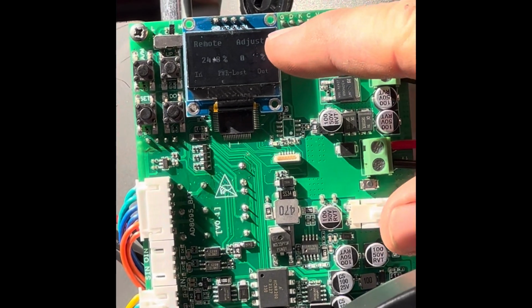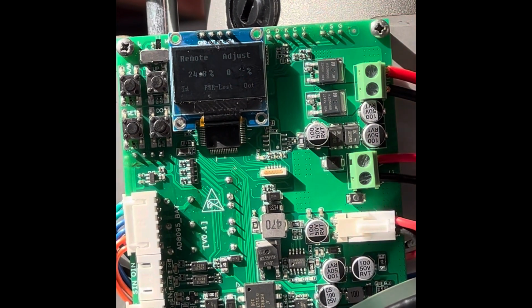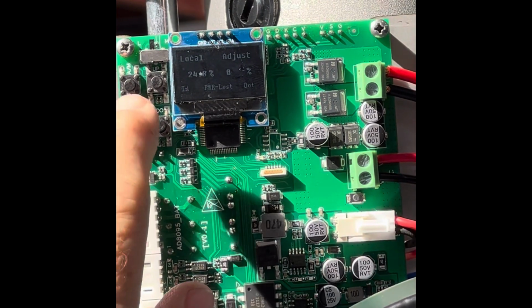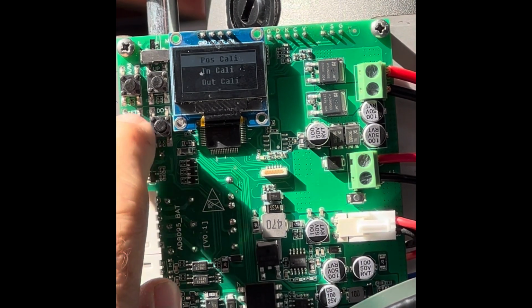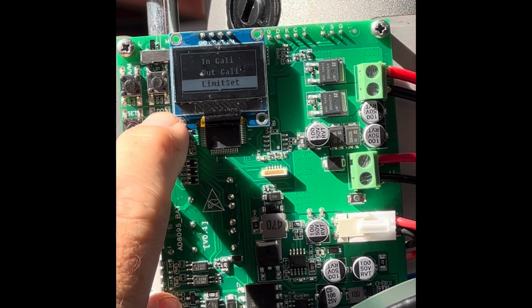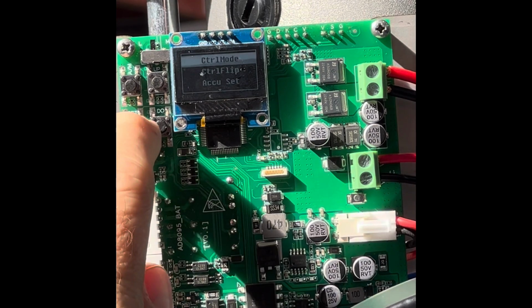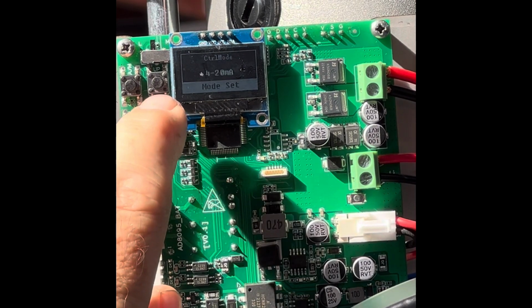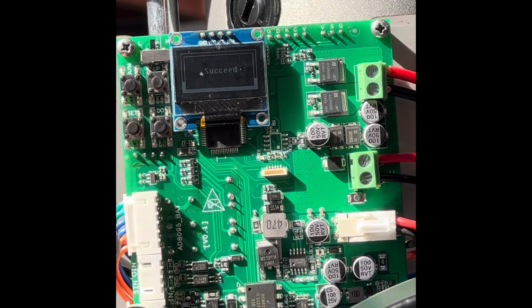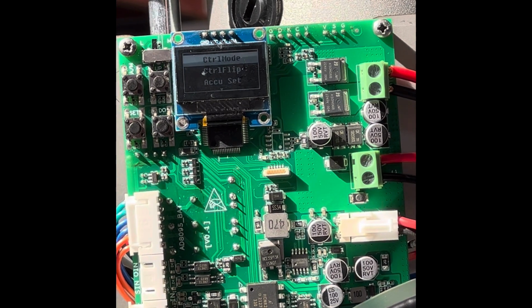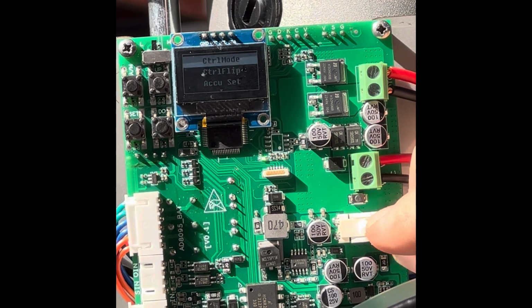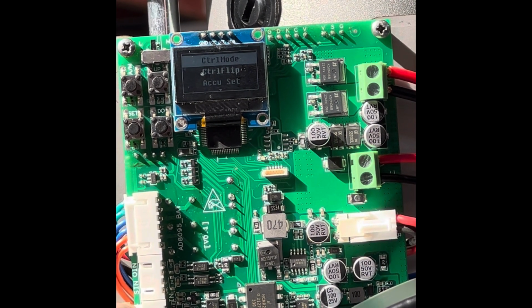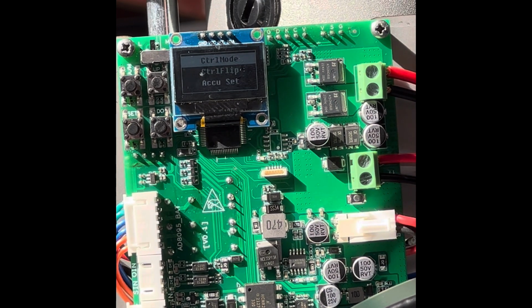To change this back to keep, you'd go back through, find your control mode. So put it to L, go to set, then go down until you see system set. The first one is control mode, set, dial it down to keep, set, go back, and here's where I'd take power off of it, unplug the battery, and then relocate this plug to this position here. Then turn power on, have your battery plugged in, and you ought to be able to give it a keep signal in the back with your dry contact.